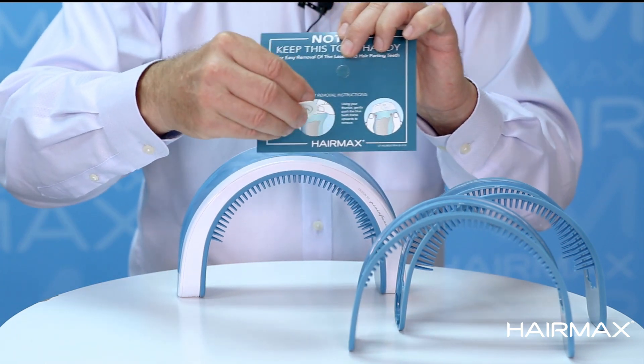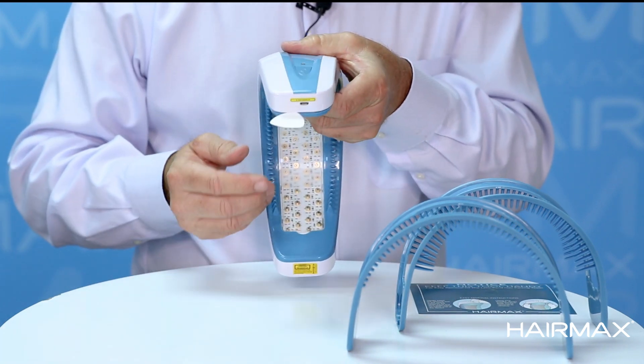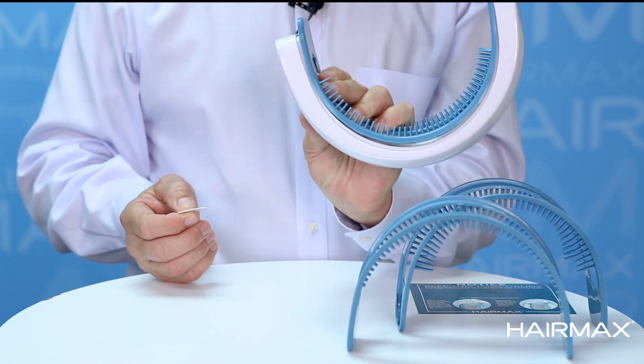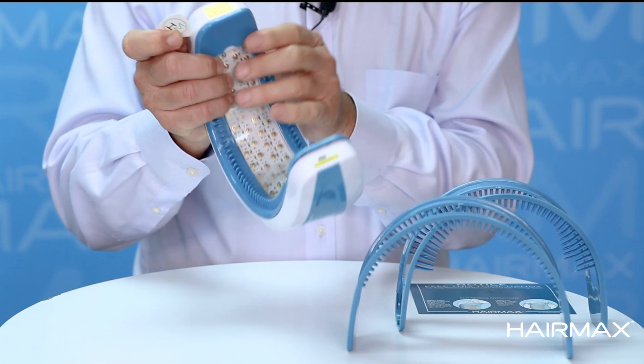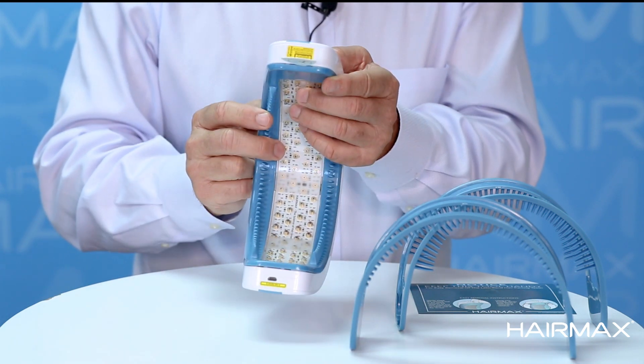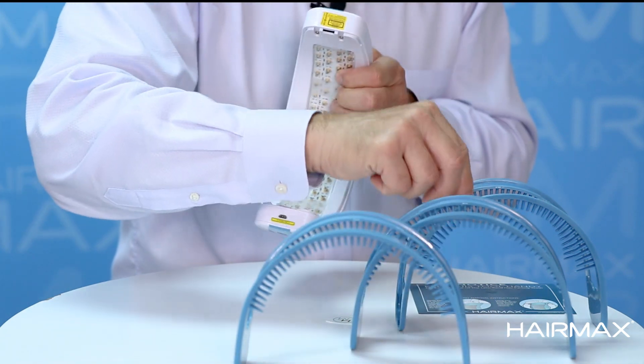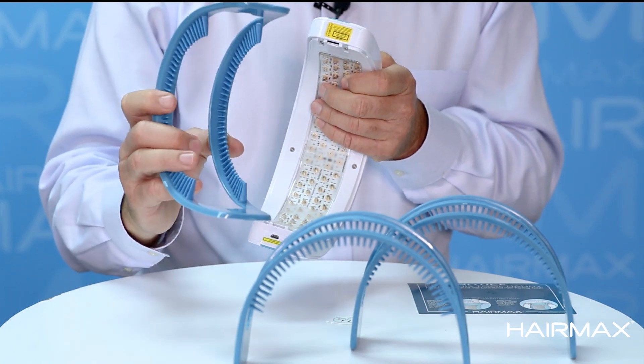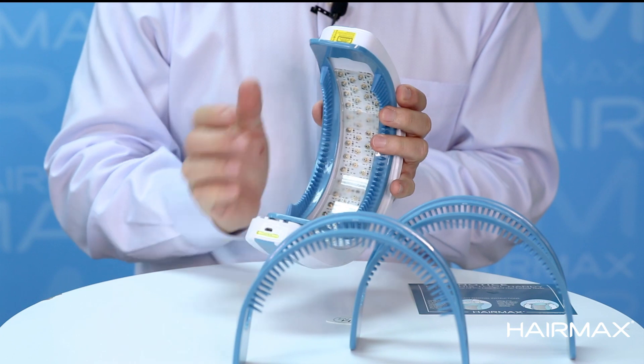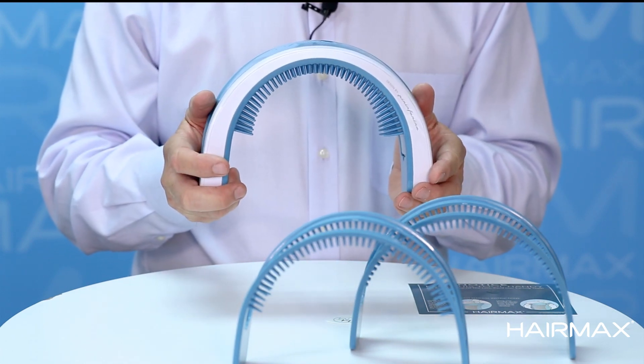To use the tool, take it off the cardboard and insert it right in between the blue and white sections where they come together. You can see how it's inserted there — that's going to release the catch and allow the teeth to slide right out. You do it on one side, then on the other. Then pick up the longer teeth for a small head. Make sure you align them — there's a little R for right and an L for left. The R has to go to the right and the L to the left. Put the teeth there and they just slide and snap right into place, and you're all set.